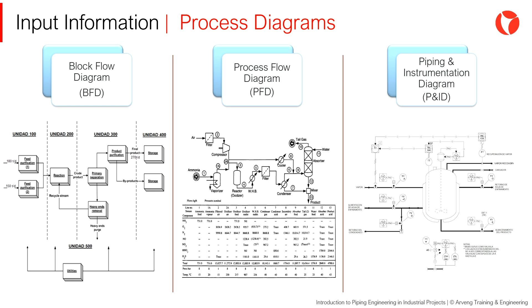The process discipline also generates an initial version of two key documents for the piping division: the line list and the equipment list. The line list enumerates each of the pipes identified from start to finish. It includes information on various process properties such as fluid, design temperature and pressure, pipe size and class, heat treatment, routing requirements, painting, and insulation requirements, as well as a unique reference number.